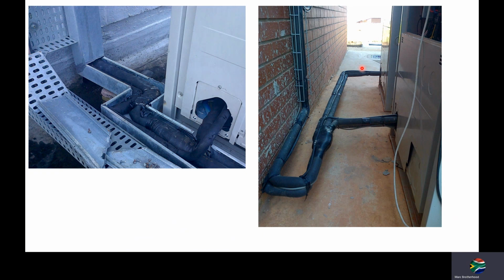Here we see these pipes are purely being supported, or unsupported, I should say. There's no supports. These pipes can just bounce up and down, up and down, up and down. With the coefficient of thermal expansion, these are going to expand. And why the installer did this very, very short radius bend, it's not ideal. You could have just come down here and then distributed off the wall. They did not need to do this very, very sharp dogleg bend. But besides that, if they did have to do that, they could have taken the pipework up here, up this wall, instead of U-turning all the way back and then going all the way up.